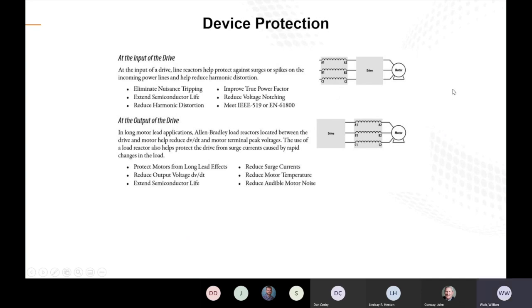Next portion here is drive protection. The next thing that you might want to consider is installing line reactors on the input or the output of your VFD. Now it can depend on the installation on whether or not you might need this. So at the input of the drive, you might want to consider line reactors if your power exceeds over 10 times what the VFD's power is rated for, or 20 times that if you have a DC link choke. You have to look here on the top right image here. That's just going to be coming on the input side of your VFD.